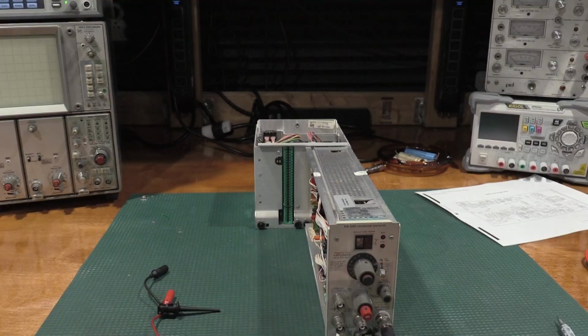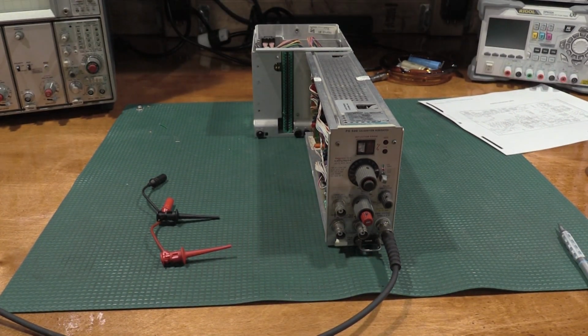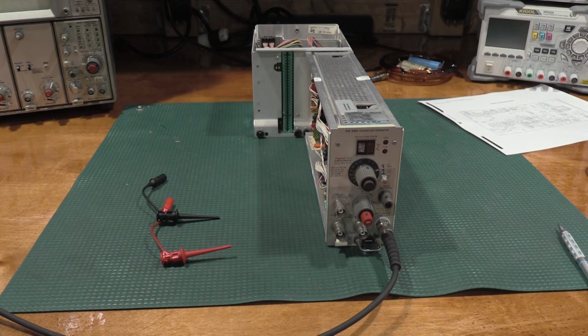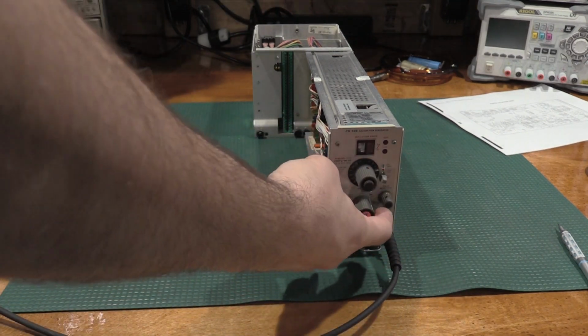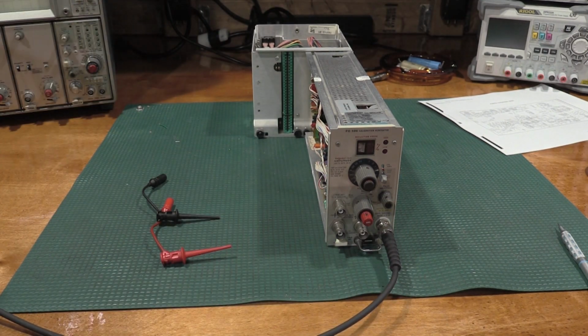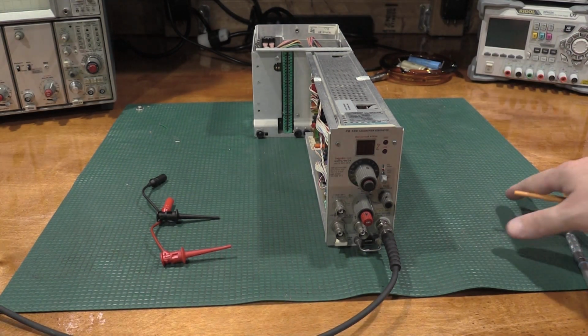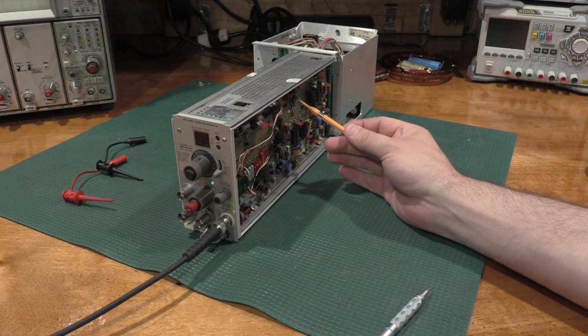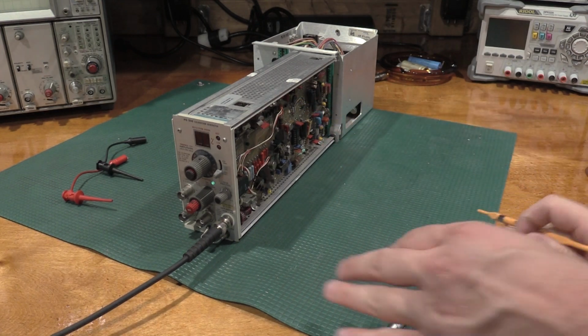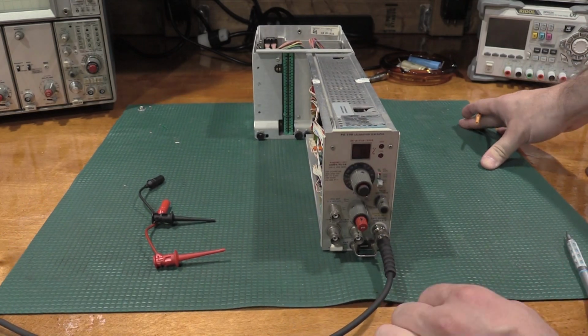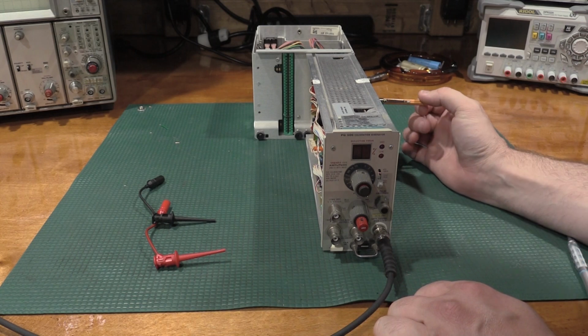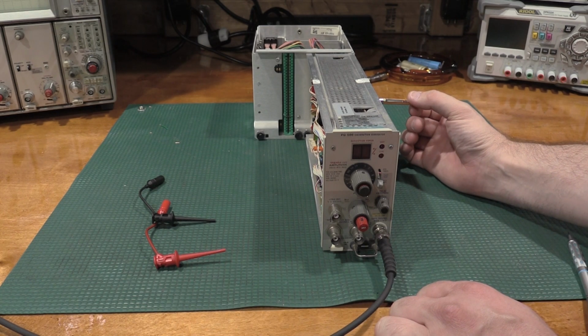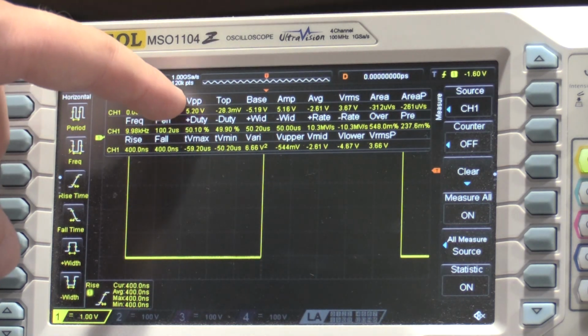Good enough for me. Okay, the next step was checking the high amplitude output unterminated, the max amplitude set into 50 ohms, R790. This was a little confusing. So they want you to pull the signal out, high amplitude, all the way clockwise, pull the signal out and send it up to a scope into a 50 ohm terminator. And you adjust R790 max amplitude set for 5.2 volts. We are a little off. R790 is right here that needs to be adjusted. We're going for 5.2. I'm doing this on the Rigol because it has good measurement. And there's our 5.2. Right, Vp peak, 5.2.